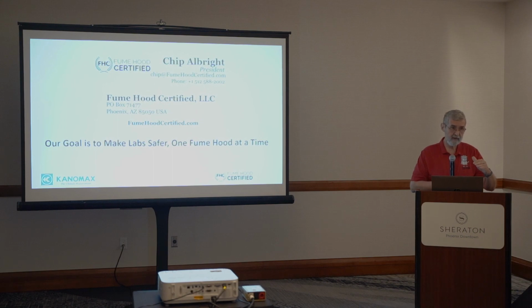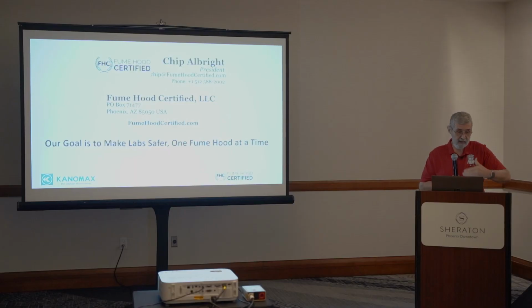What I was realizing was that it was sucking out of the vortex, going over the top of the sash and being pulled down the face of the sash, right through the user's breathing zone, and then back into the hood. So I thought, well, that's interesting. I wonder how much that leakage is. So I get my SF6 equipment out, I set it in the hood, and what do I see? Flat line, 0, 0, 0. And I'm going, it can't be. I see the escaping smoke coming out, so it can't be.